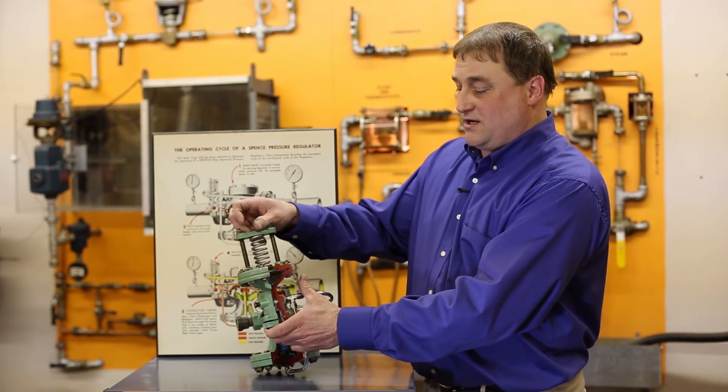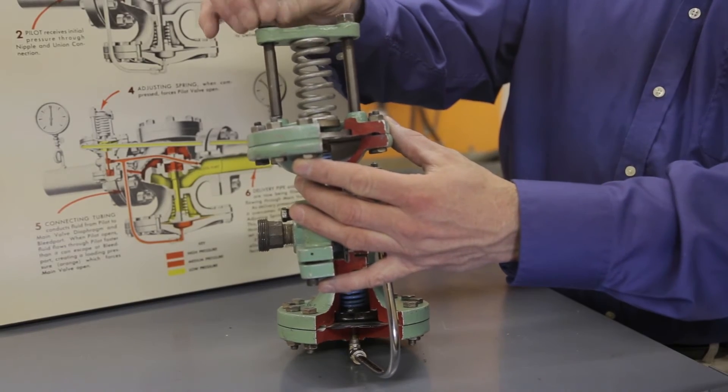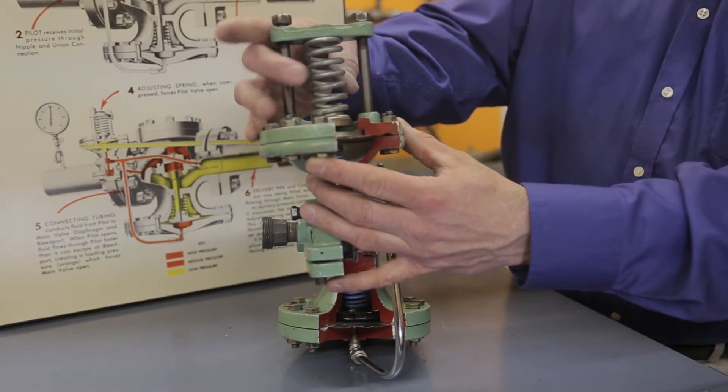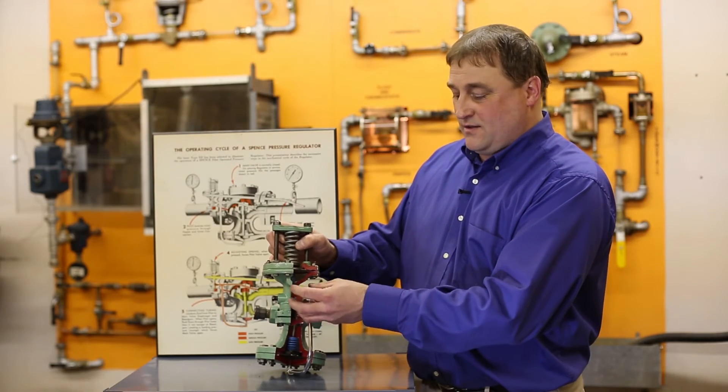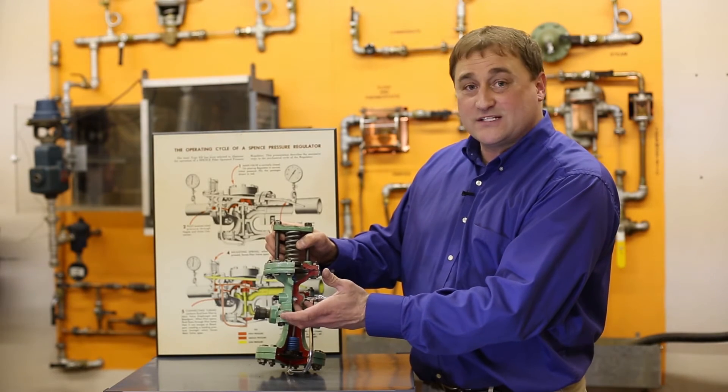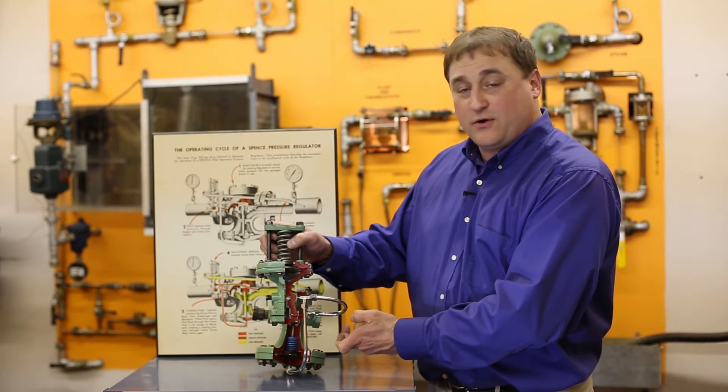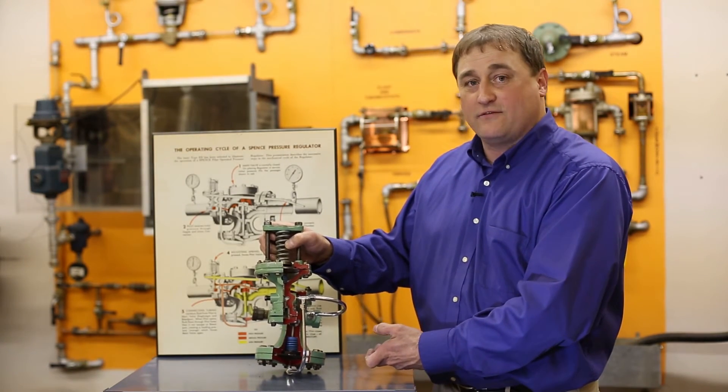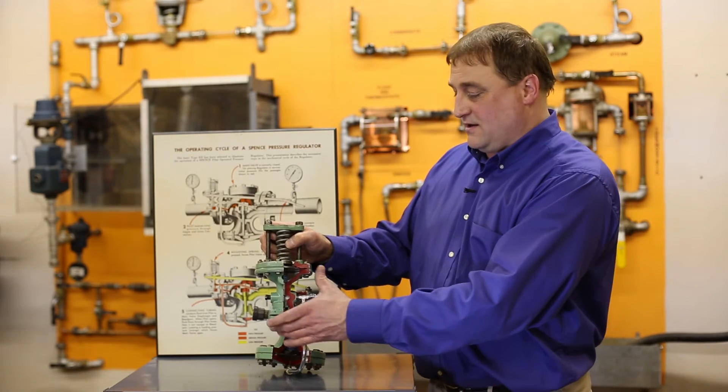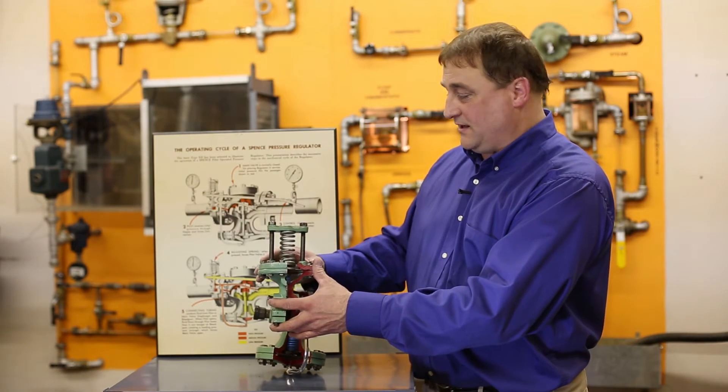When we loosen up the adjustment nuts on top of the pilot, we then relax the spring. The pressure goes down. The pressure inside says that it is now satisfied, and it will allow the pressure to start to reduce and fall off, so we can adjust that pressure as much as we would like.